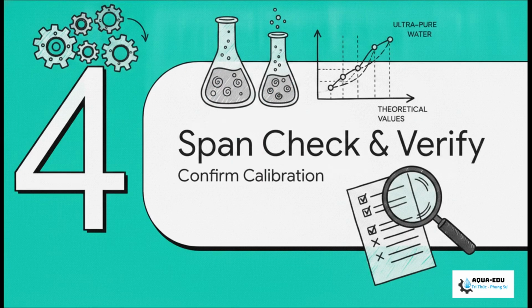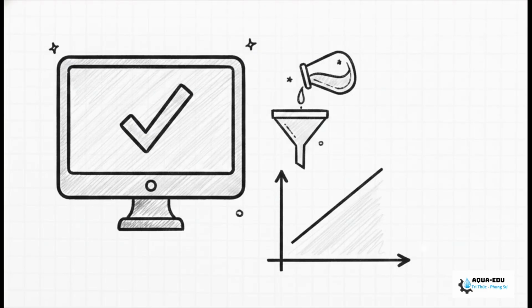Section 4. Span check and verification. So the span cycle's just wrapped up and you've logged your values in percentage error. Now we actually have to verify that the calibration was a success. You're specifically looking for a green span check pass banner to pop up. But brothers, we do not stop there. It is absolutely vital to run an independent check solution, something like a 250 ppb carbon solution. This independent verification is what actually proves the sensor's linearity across different concentration levels.